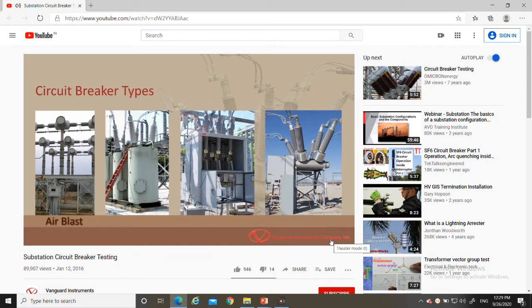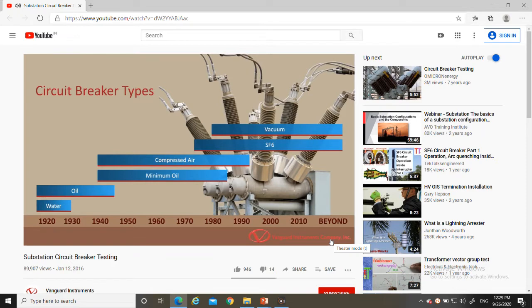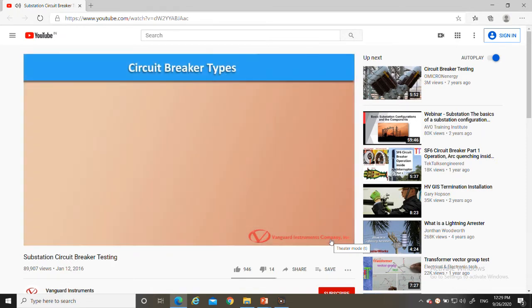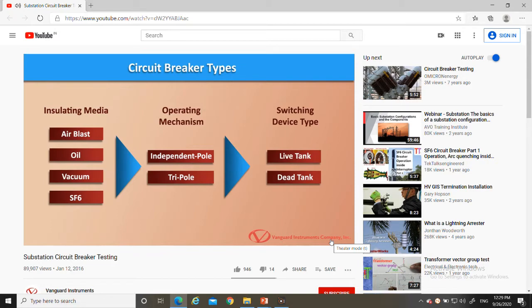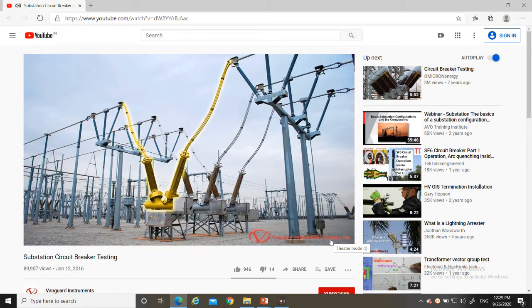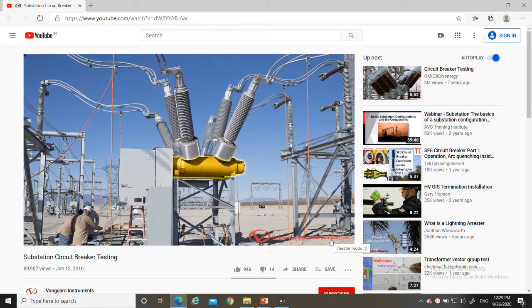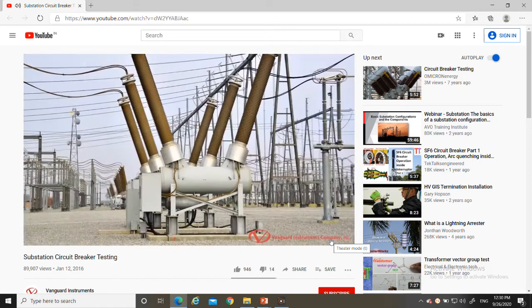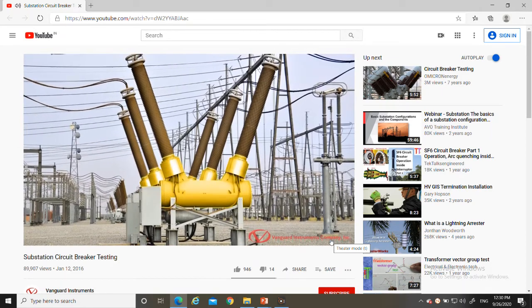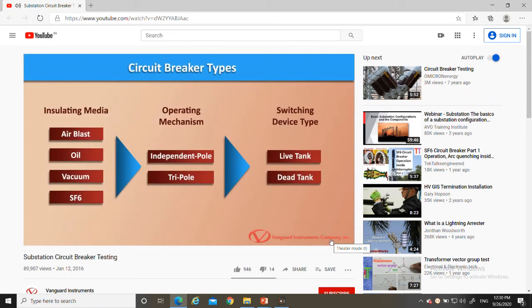The four main breaker types are: air blast, oil, vacuum, and sulfur hexafluoride (SF6). Most breakers today are either vacuum or SF6 due to their smaller size. Substation breakers are classified as either independent pole or tri-pole, and further classified as live tank or dead tank. Live tank breakers use a vessel at potential above ground, while dead tank breakers use a vessel at ground potential surrounding the interrupter and insulating media.